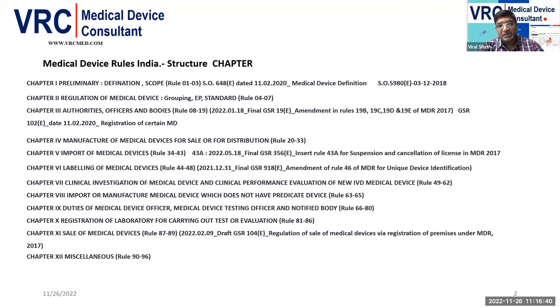In some cases, clinical investigation is required when you claim that your device is somewhat different from the already approved device, and the indication of use is somewhat different, claiming a new device. So if you are manufacturing or importing a new device, in those cases clinical investigation is required.